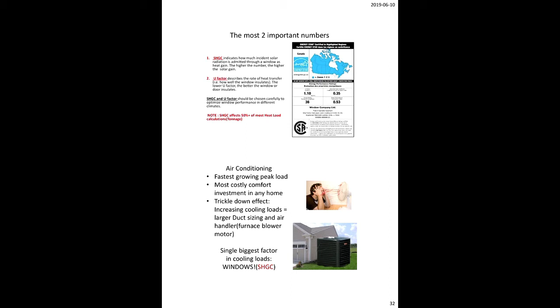A little sample of this was on an existing home. The homeowner had the choice of picking a window retrofit. He got a window that was very energy efficient, had a 0.68 solar heat gain. We've seen windows in Ontario at 0.71. When they put the new windows in, it would have meant he needed 4 tons of air conditioning in the house. He went back to the window manufacturer and said, actually, I'd like a solar heat gain mid-range. Can you get it to me? He says, sure, why would you want that? He said, well, I just need it. He says, will it cost me any more? No, that's our baseline. Went back to 0.32. They're now at a 2.5 ton unit.